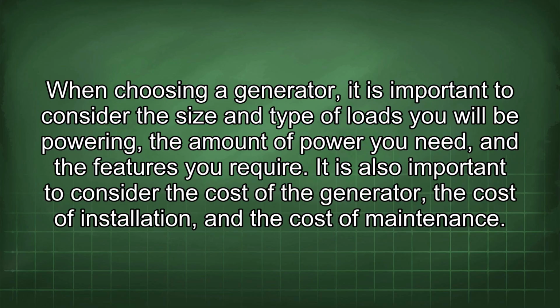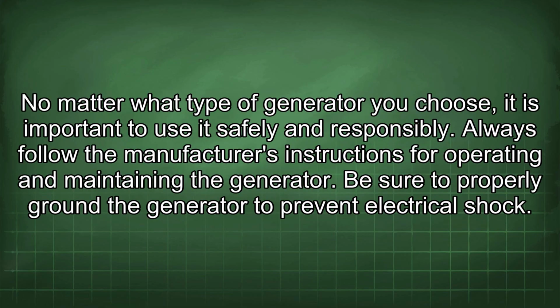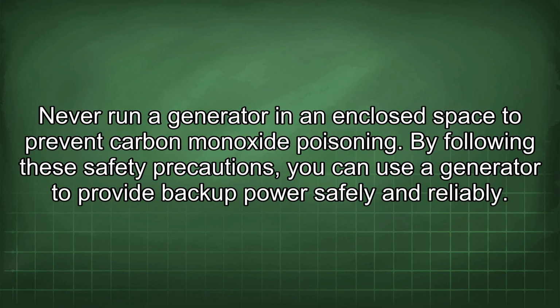When choosing a generator, it is important to consider the size and type of loads you will be powering, the amount of power you need, and the features you require. It is also important to consider the cost of the generator, the cost of installation, and the cost of maintenance. No matter what type of generator you choose, it is important to use it safely and responsibly. Always follow the manufacturer's instructions for operating and maintaining the generator. Be sure to properly ground the generator to prevent electrical shock. Never run a generator in an enclosed space to prevent carbon monoxide poisoning. By following these safety precautions, you can use a generator to provide backup power safely and reliably.